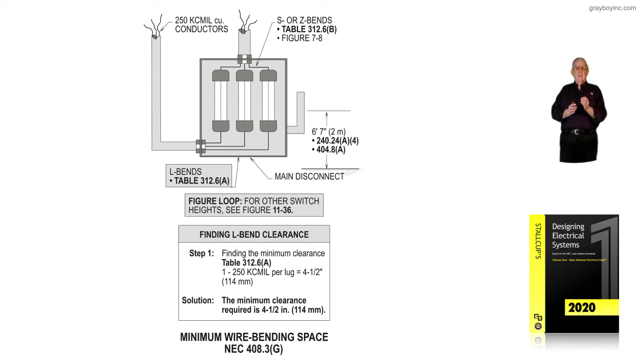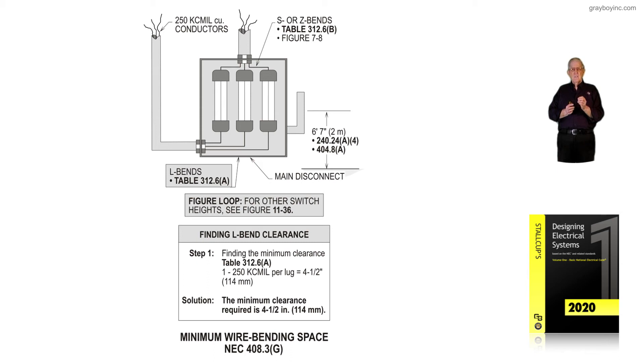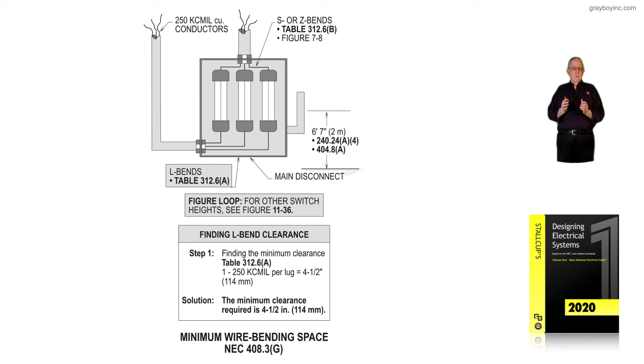NEC 404.8A covers the 6'7" rule we're looking at. If we are finding the clearance requirements in inches for the L-bend, we go to table 312.6A, and one 250 KC mil per lug is 4½ inches. So in the solution, the minimum clearance required is 4½ inches. Many times an inspector will go to 110.3A3 to deal with this minimum bending space, and it has to be provided in all enclosures, panelboards, and so forth.